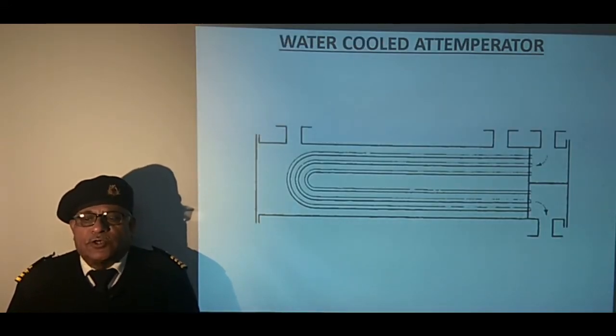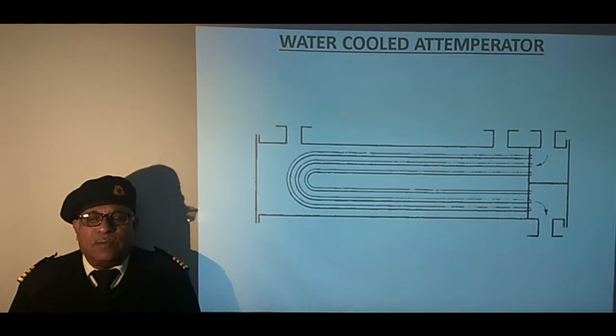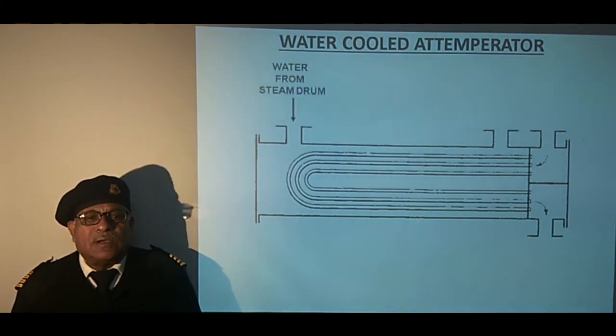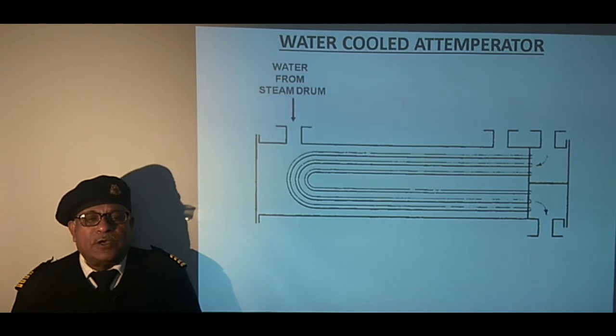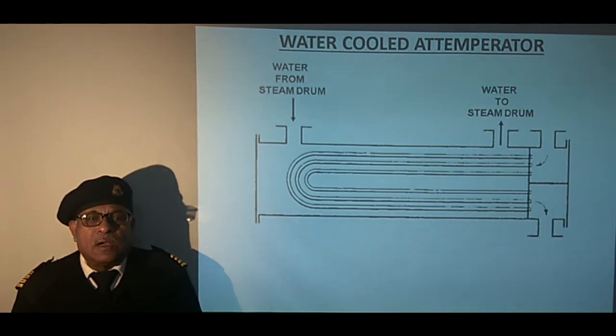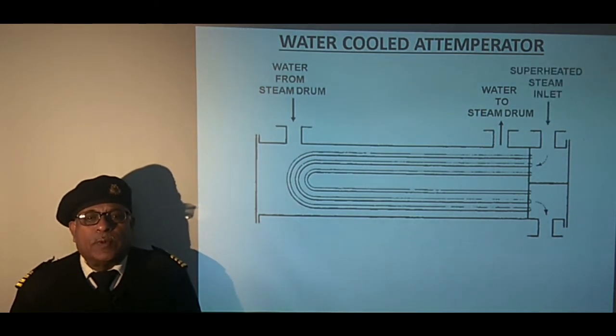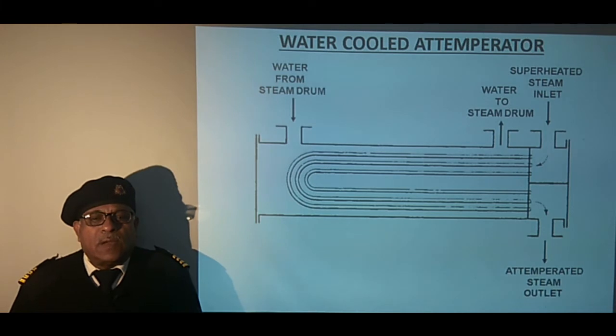This sketch shows an externally arranged water-cooled attemperator. Let us first see the flow of steam and water through it. We can see that water from the steam drum enters the shell of the attemperator. Then from the other connection, it goes back to the steam drum, and the circulation is maintained by the temperature difference. In the header, the superheated steam enters from the top and the tempered steam goes out to the secondary superheater.